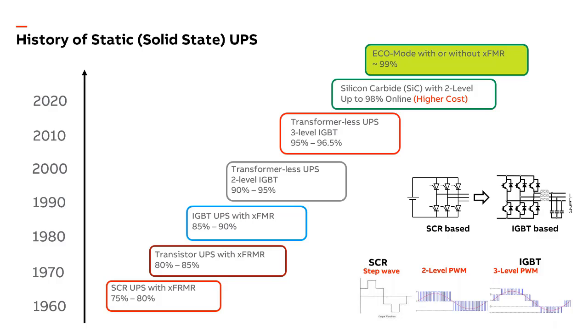In today's world, like the third box from the top, the red circle that states transformerless UPS 3-level IGBT, that's where practically all manufacturers are today. Most UPSs, and this is true for all ABB UPSs, are around 96.5% efficiency, give or take a little bit, but it's in that area.